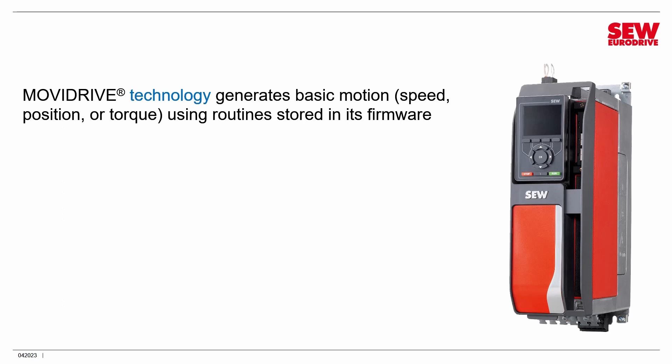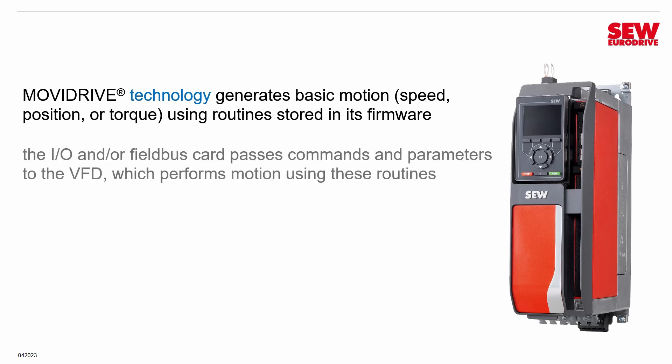Whichever mode you're using to control it, it generates its basic motion — by this I mean speed control, simple positioning where it just goes to a specific location, or torque control where it maintains a fixed torque — using routines stored in its firmware. In other words, it's built-in software. Its inputs and outputs and/or its fieldbus card pass commands and parameters to the VFD, and then it performs motion using those built-in firmware routines. That's pretty much the whole show for Movidrive Technology.